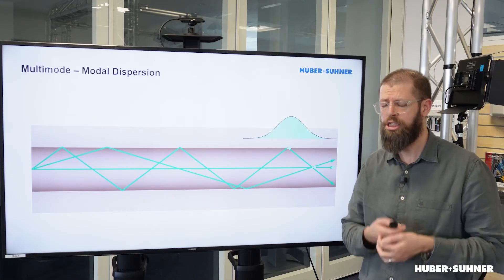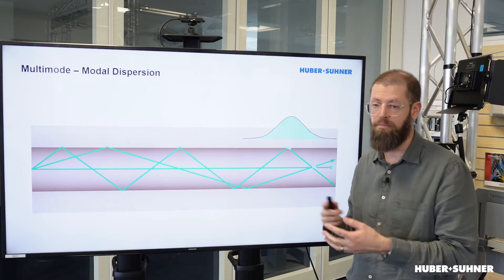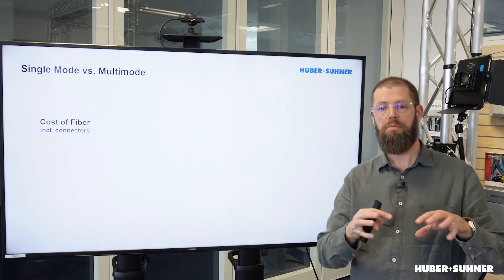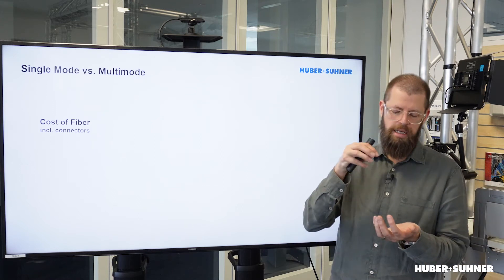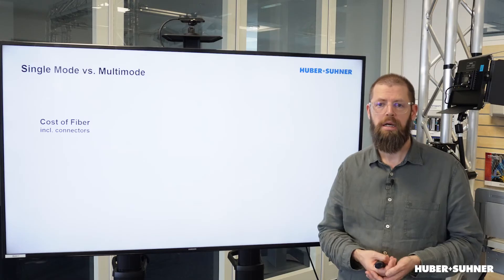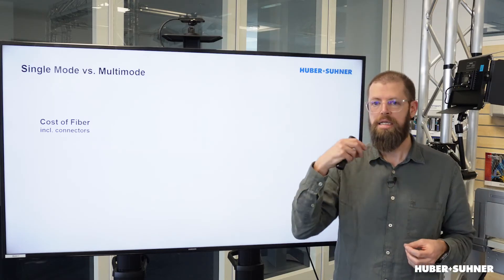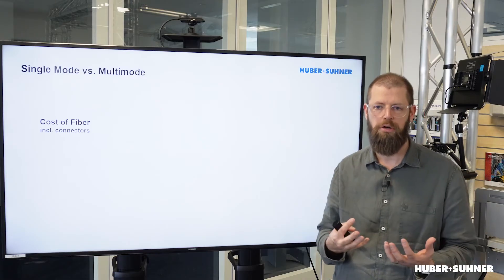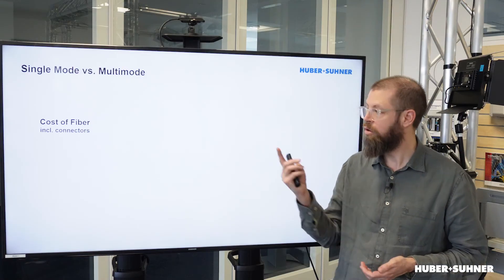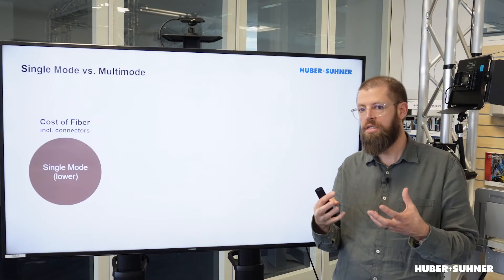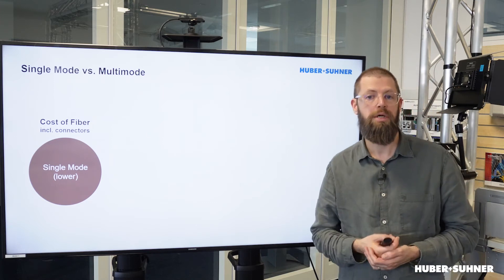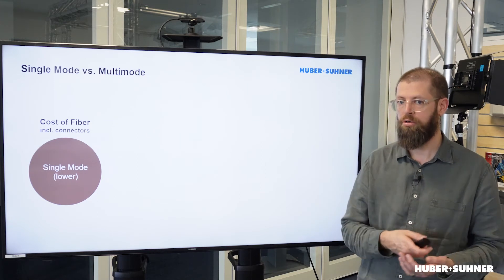So why do we still use both single-mode and multi-mode? Let's start with the cost of fiber. For a long time it was stated that multi-mode is more cost-effective than single-mode because the manufacturing process is simpler. But that's not the case anymore, because single-mode is being manufactured in much larger volumes, meaning the cost difference is now negligible. Also, for multi-mode we are using more complex connectors — MPO and MTP — whereas for single-mode we generally use LC connectors, which are much more cost-effective.